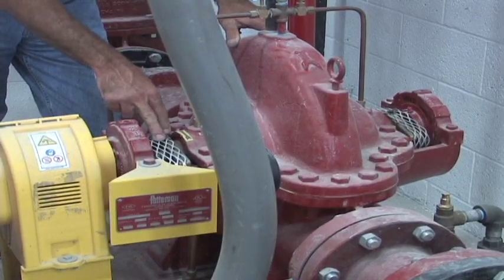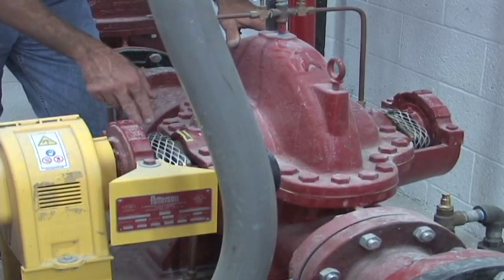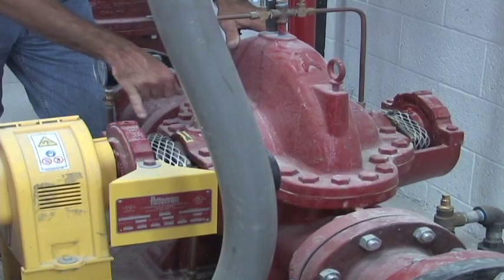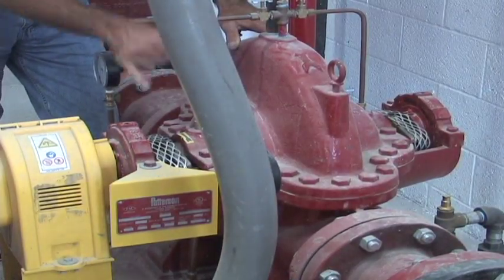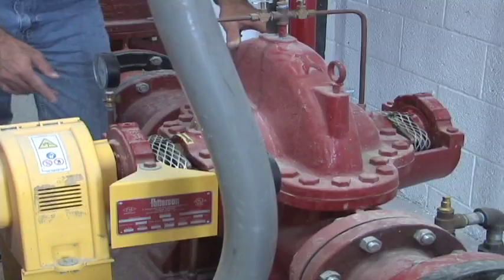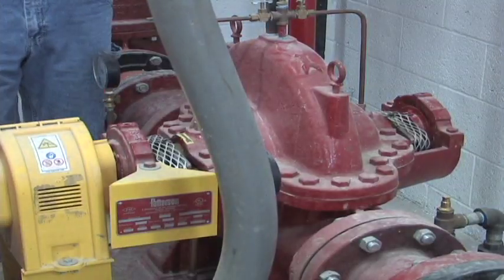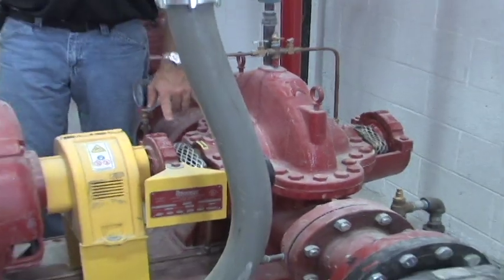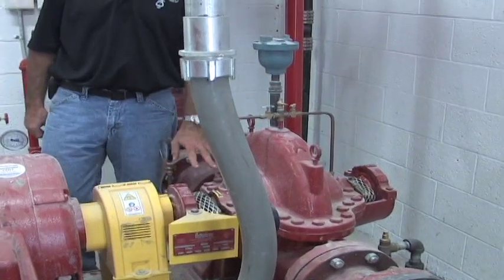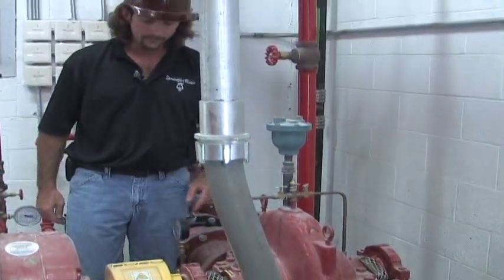So we got to make sure that we keep the drip cups clean, the 1/2-inch hole on the inside and the outside, and the annual grease on the front, the inboard and the outboard, that we change out only on the annual basis. We don't pump any grease into it on the monthly basis, strictly just annual.